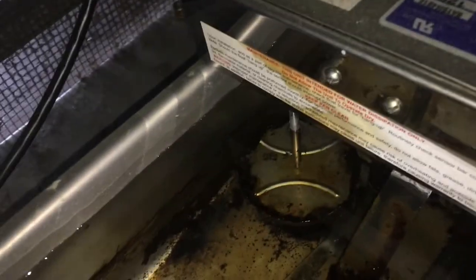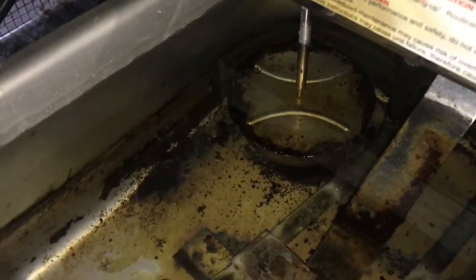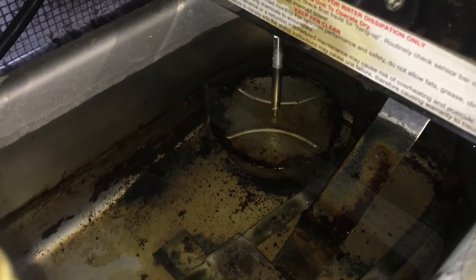Only like a six-month-old condensate thing and the float has sunk — it's not floating. I corroded it out probably again. There's a piece of junk in it. A piece of junk.